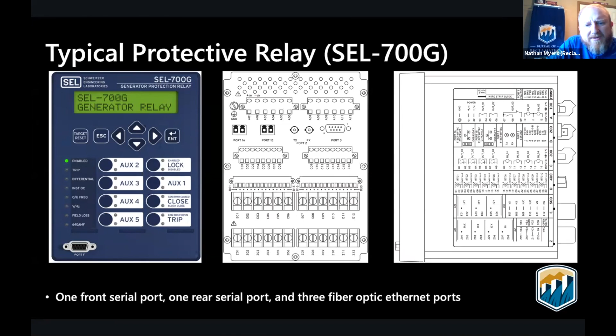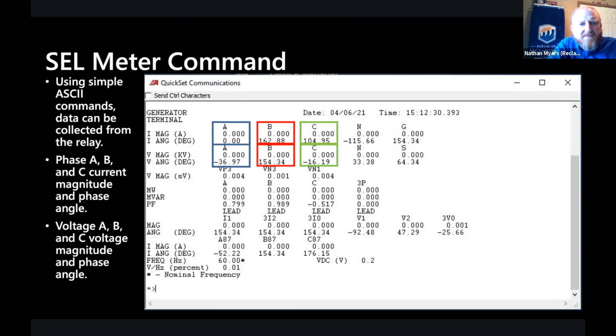What we're going to want to be able to do, for example, within a SEL relay is it uses ASCII commands. And you can log into a relay and type a meter command. And this shows you an example of the data that you would get when you type meter within a SEL relay. You can see we have A phase voltages, A phase current, B phase voltage, B phase current, C phase voltage, C phase current, as well as other values. What we're able to do is parse the data from these meter commands and bring that into the centralized challenge device, the device that you guys are helping us come up with. And we'll be able to compare these voltage magnitudes and current magnitudes to ensure that they're similar to one another. Next.